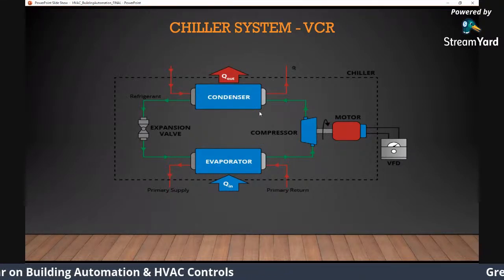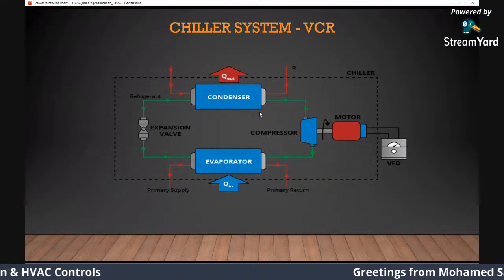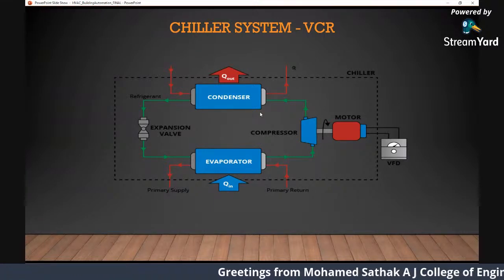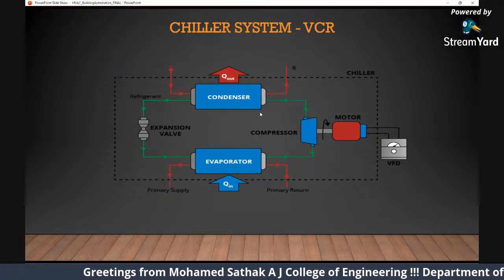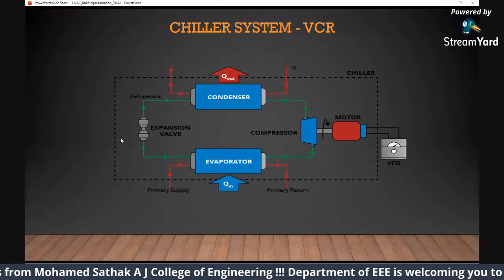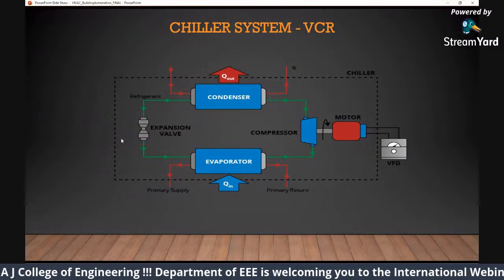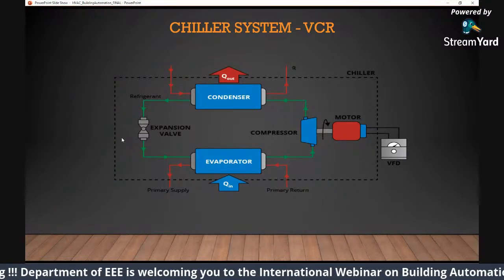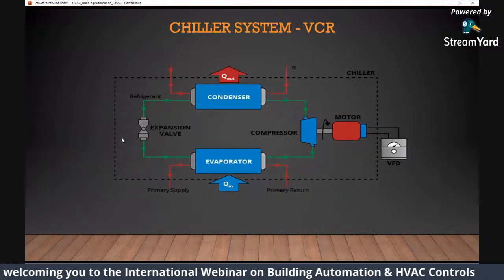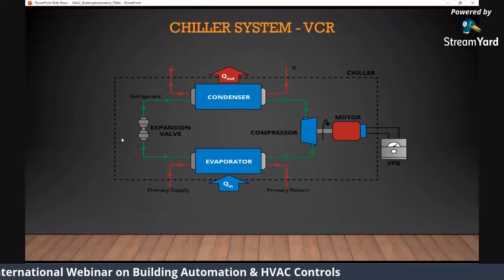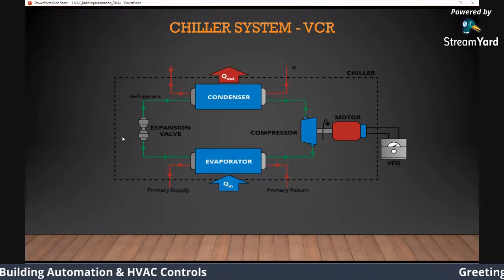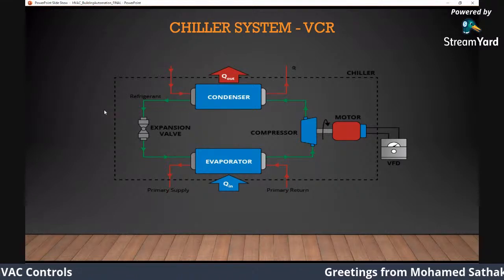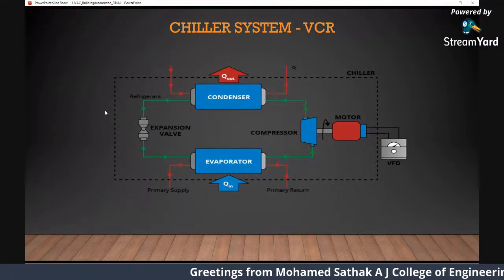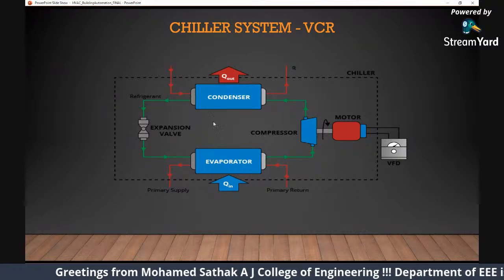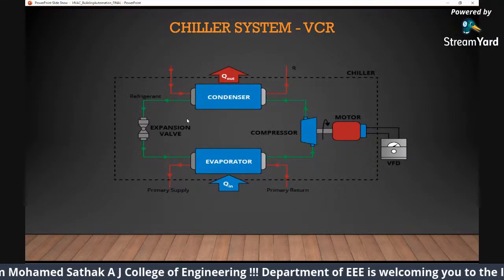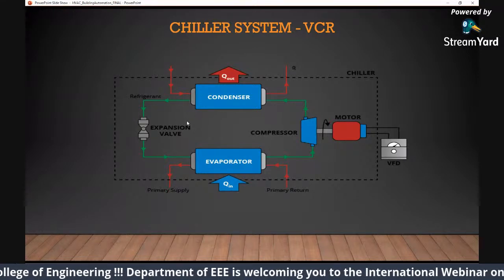So I'm not going to get into detail again, but this is a typical VCR cycle you should have known. This is the principle that the chiller operates on. We have a refrigerant in a chiller. There are many government rules and laws behind it, because refrigerants cause greenhouse gases and are bad for the ozone layer. I'm not getting into detail again, but the major thing used in a chiller is the refrigerant, which cools your water to a very low temperature. And the principle behind the chiller is again the vapor compression cycle.